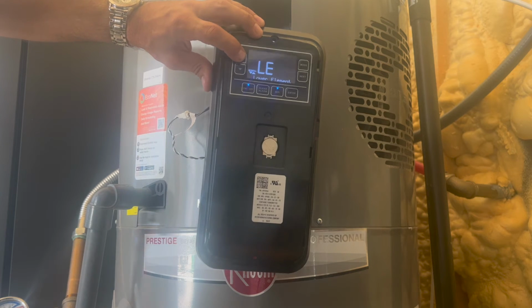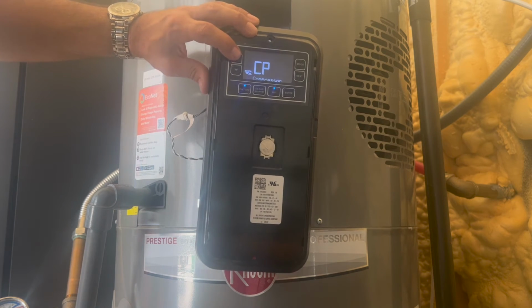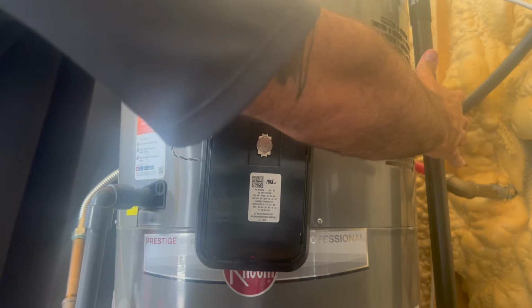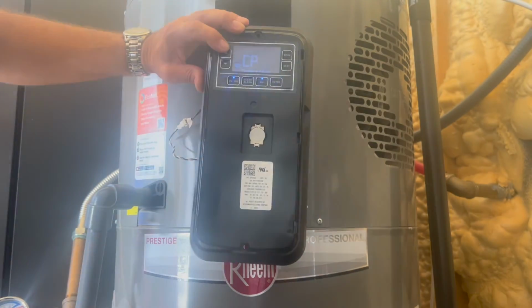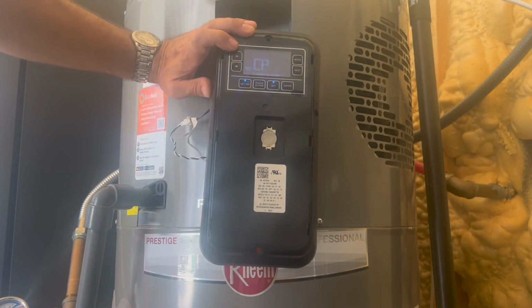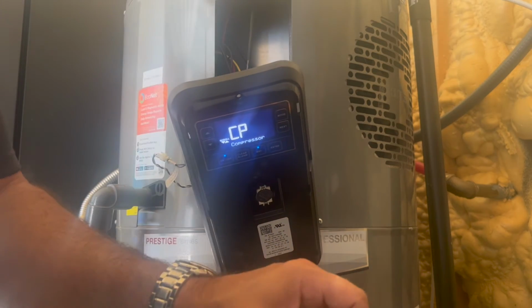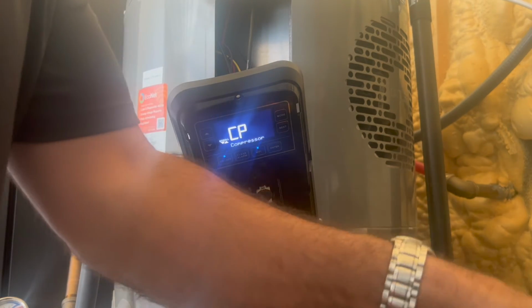Upper element, lower element, compressor. Compressor kicks on. Like I said, the fan should also kick on. I can hear the compressor running. I can feel the air blowing off of the fan. Right. Let's see what our capacitor says.